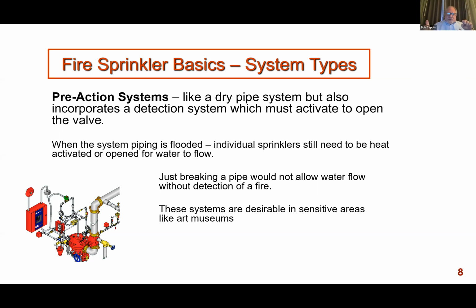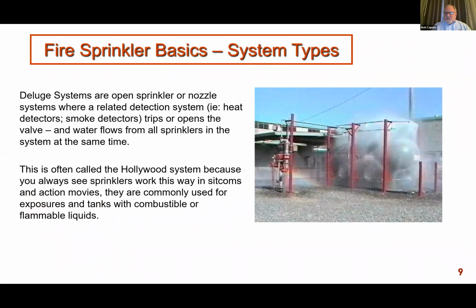I have the heat for the sprinkler, and I have the detection system function that opens the valve through a solenoid and then floods the system. Most of my sprinklers are still closed, but the open sprinklers are then going to flow water. Now, in my pre-action and in my dry pipe systems, I have a bit of a delay, about 60 seconds or less, before water hits the floor and acts on the fire. So in those cases, my design area is going to be a little bigger. And again, sometimes I get in the weeds and tell you too much information.